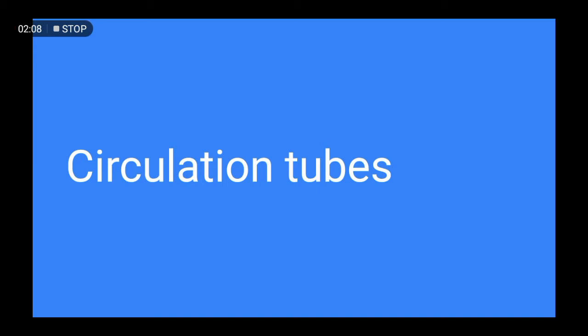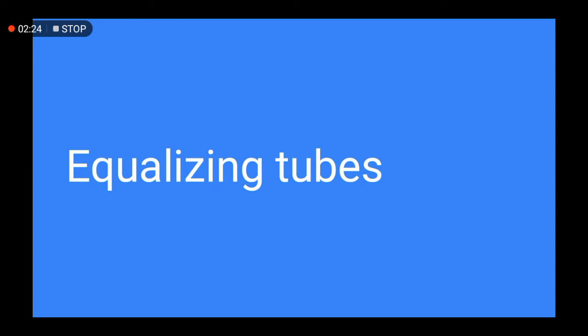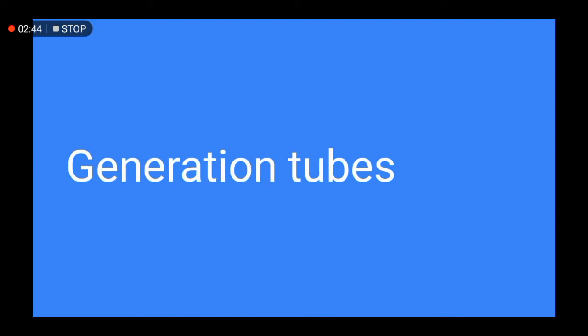Circulation tubes are used in Stirling water tube boilers for continuous circulation of water. They play a very important role because good water circulation is a key feature of this boiler, which separates it from other types. Equalizing tubes have two functions: the first is to connect the steam drums, and the second is to help the flow of water along with the circulation tubes.